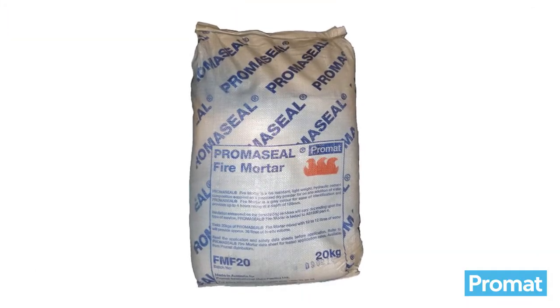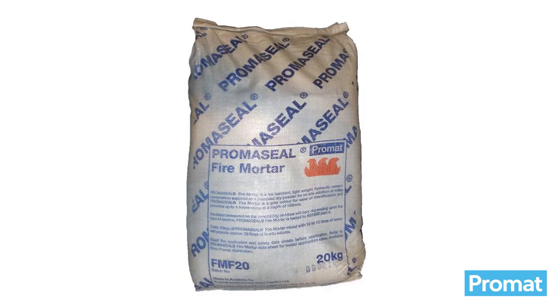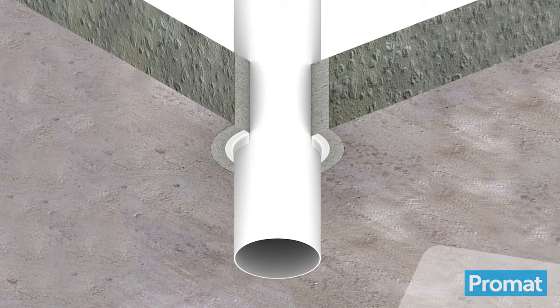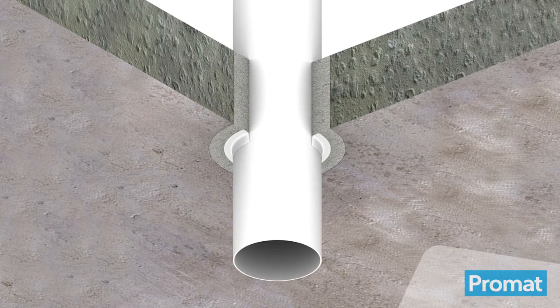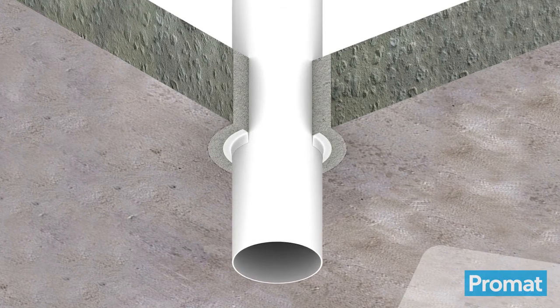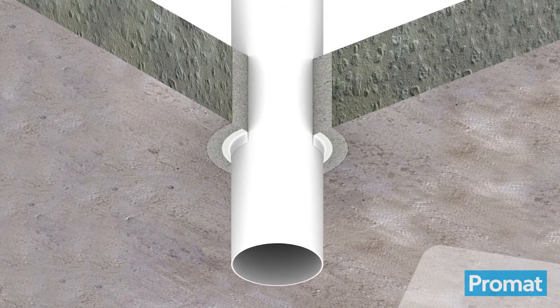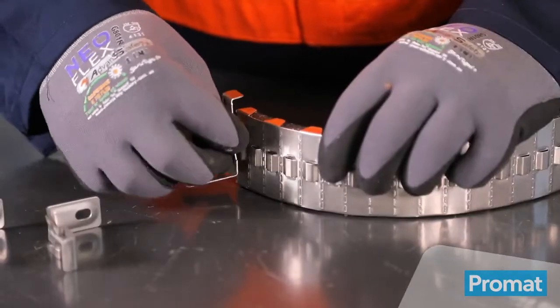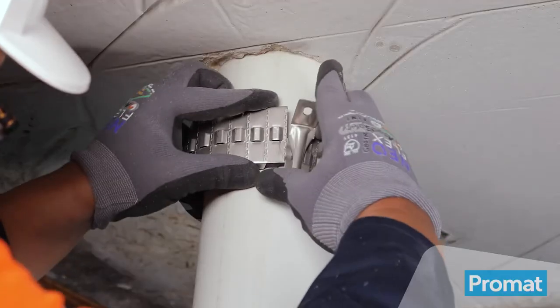Backfill any gap between the pipe and the concrete greater than 8mm wide with Promaseal mortar. If the gap between the pipe and slab is less than 8mm, apply a bead of Promaseal A acrylic sealant approximately 8mm deep into the gap on the underside of the slab.